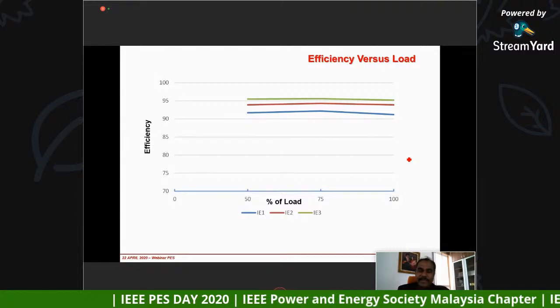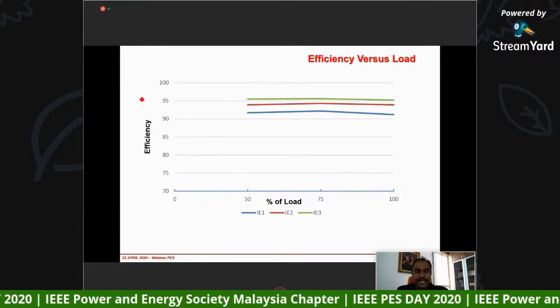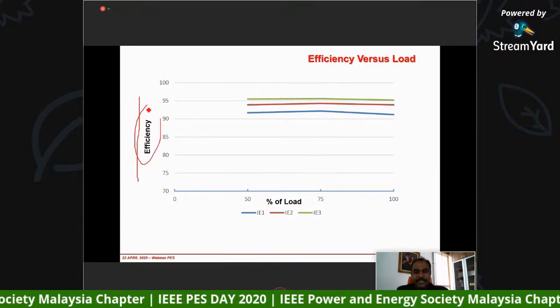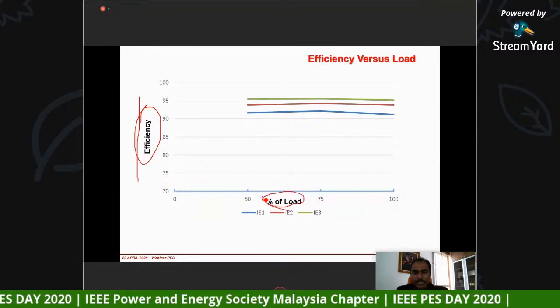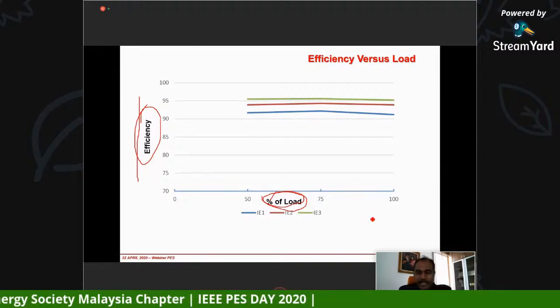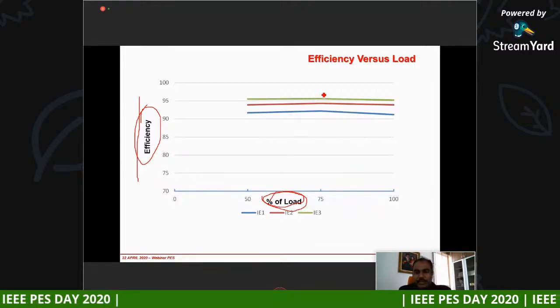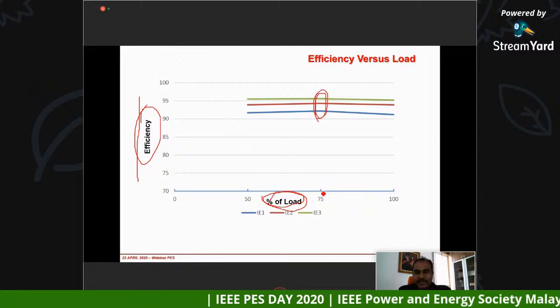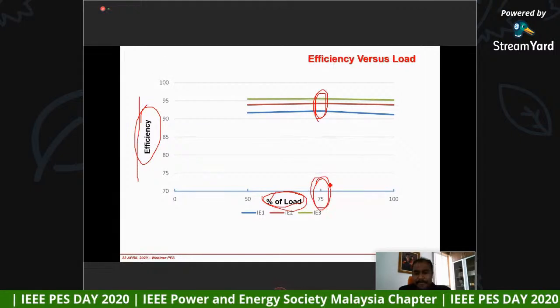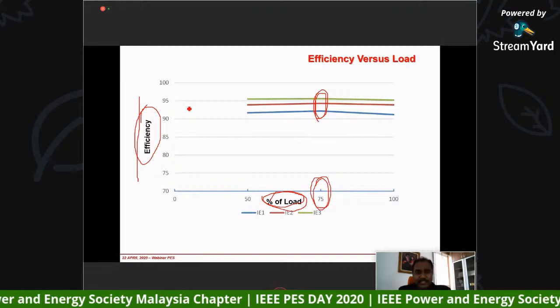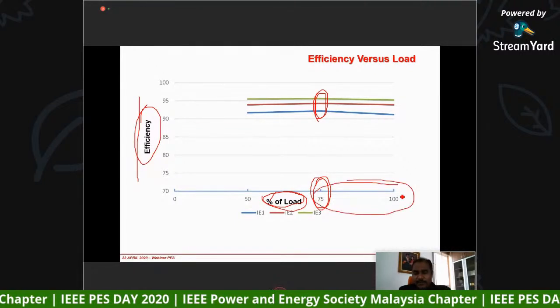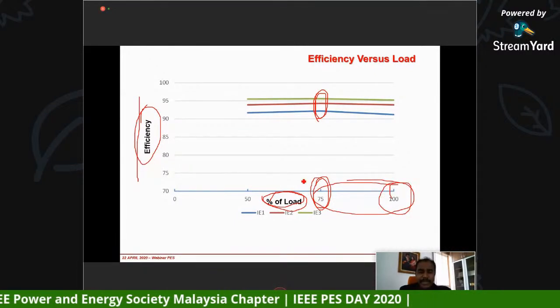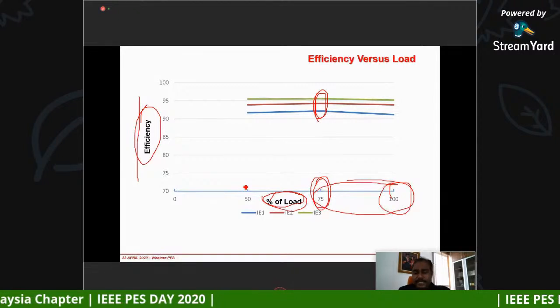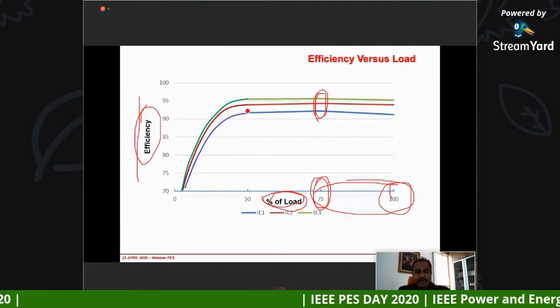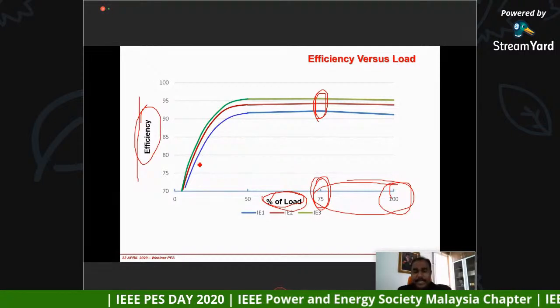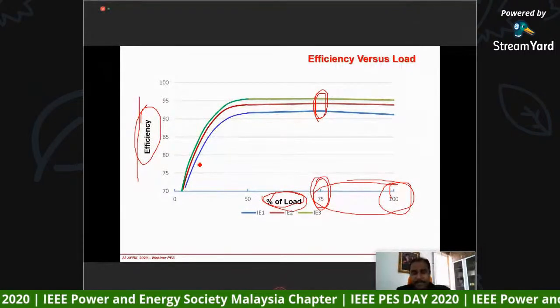And if you look at this particular curve, we have the efficiency versus load of the motor. What is the load? The percentage of load we are connecting to the motor. If you notice, usually the optimum is about 75% for the motor, and it will have reasonably good efficiency up to the full load. But when you go below, especially when you go below 50% load, you will notice that the efficiency will start to drop. That means just imagine.